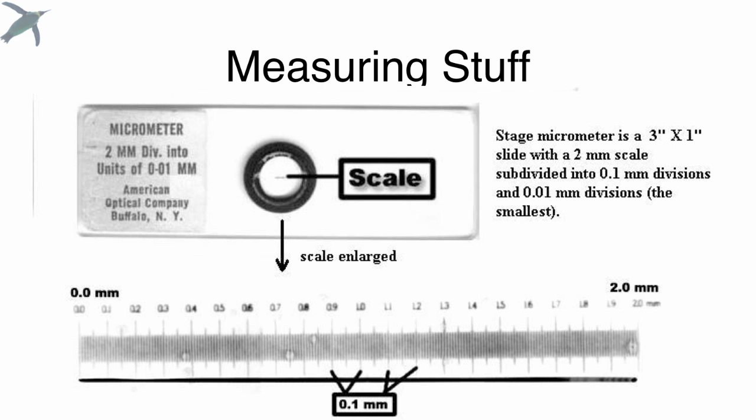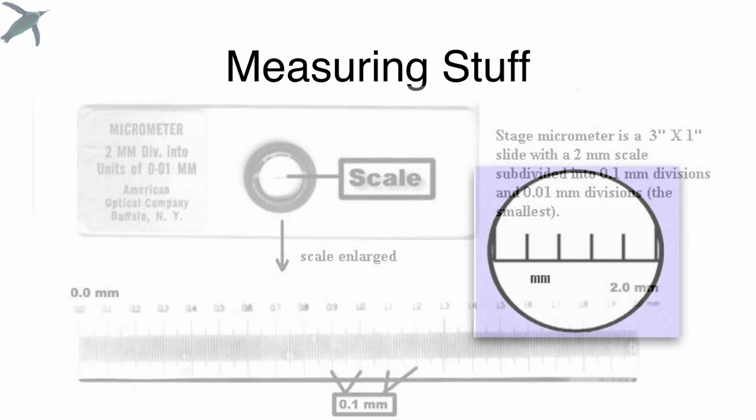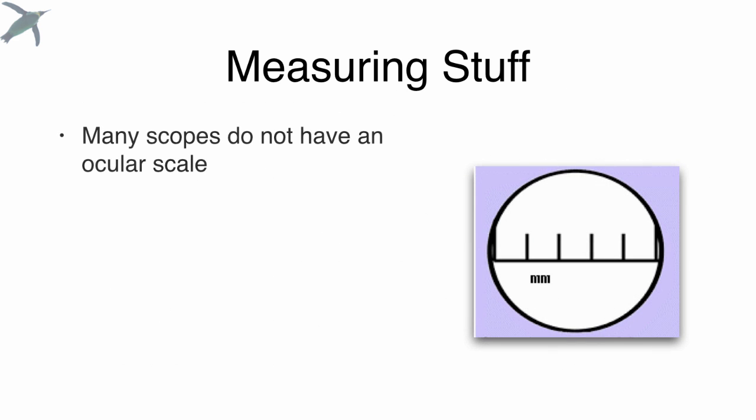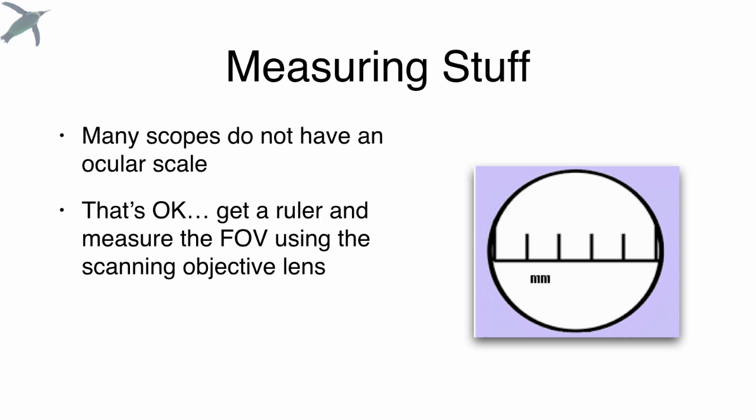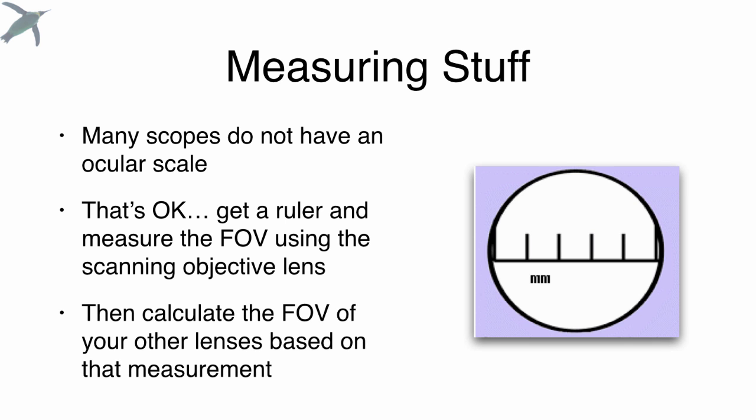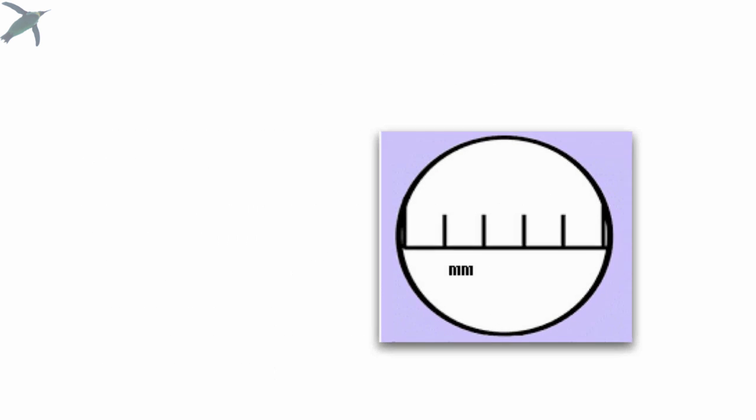All you need is a small, clear, plastic metric ruler. And what you're going to do is measure the field of view under the scanning objective lens. And then based on that, you will be able to calculate the field of view for all your other lenses. So I want to show you how to do that.